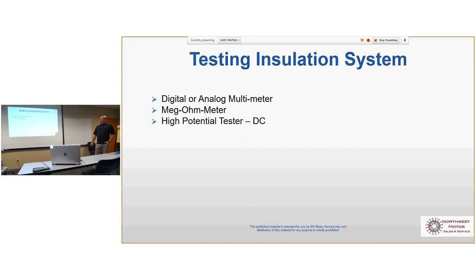So another test people do is a high pot test. It's kind of like when you take your Megger up to, if you have a 480 volt motor, and you go up to the 1000 volt scale, you're putting higher than the operating voltage on the motor and seeing if it breaks down at that point. So if you passed at 480 volts at 500, then you take it up to 1000 volts, and maybe you're starting to see that the reading doesn't look so good. It's telling you that there's some weakness there.